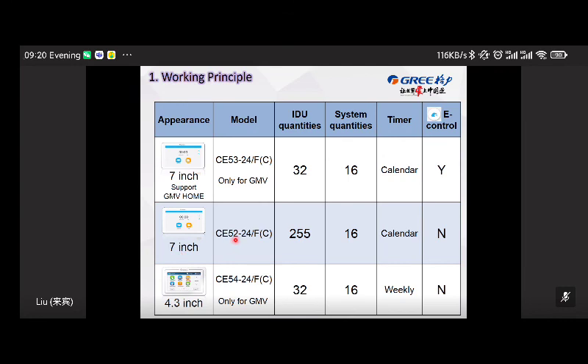The second one is the CE52, a larger 7-inch central controller. The maximum quantity is 255 indoor units. Here the limit is bigger. Yeah, it's bigger for the size of your project. However, this one is without the e-control function. The next one is the 4.3-inch central controller. It's only for GMV5. For the quantity, maximum 32, system 16. However, this central controller only has the weekly timer, no calendar.